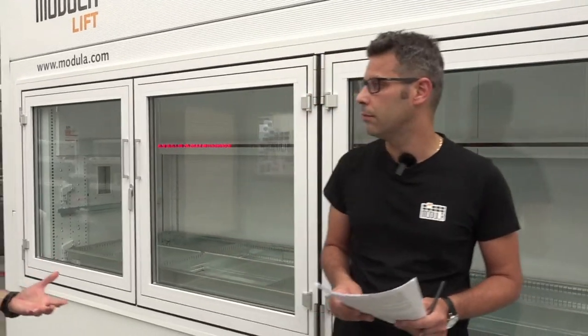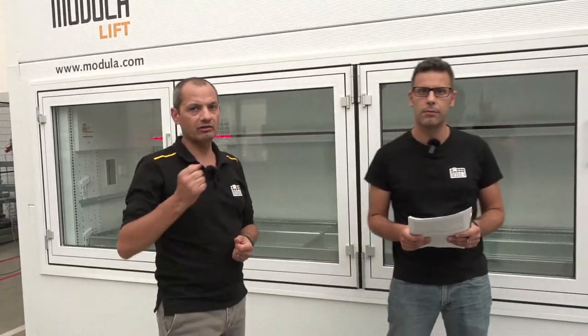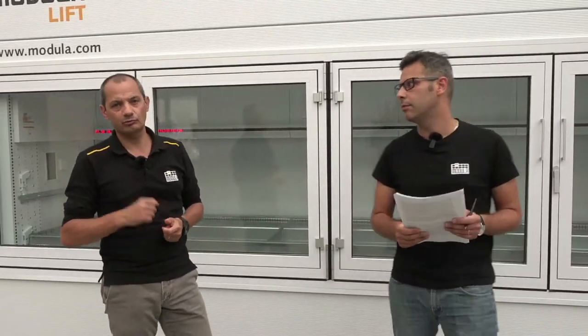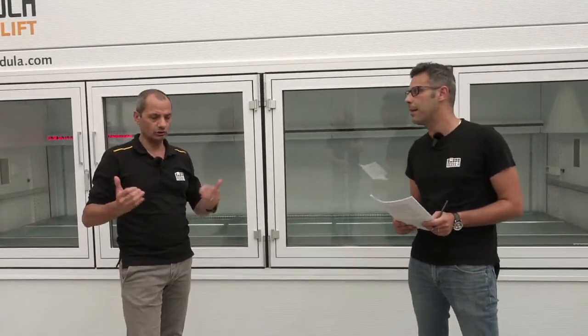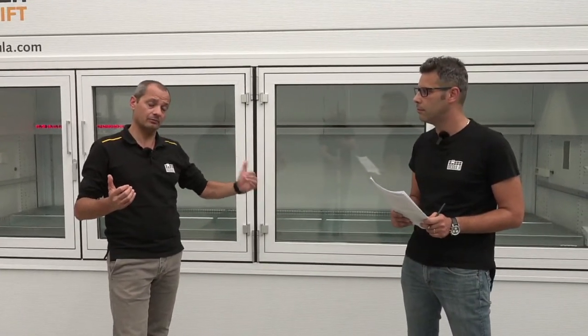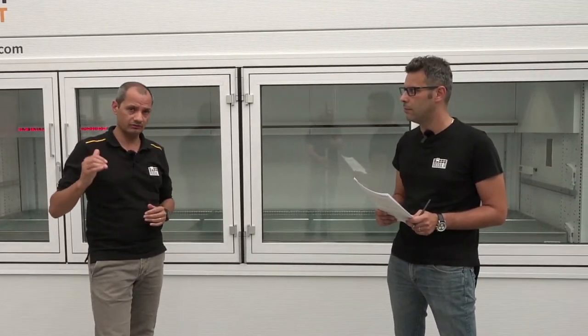So one thing that is basically not possible to reach is having 5% relative humidity at a temperature of, say, 5 degrees centigrade — that's something we cannot reach. So the two limits are 5% relative humidity and around 25 centigrade, right? Absolutely.